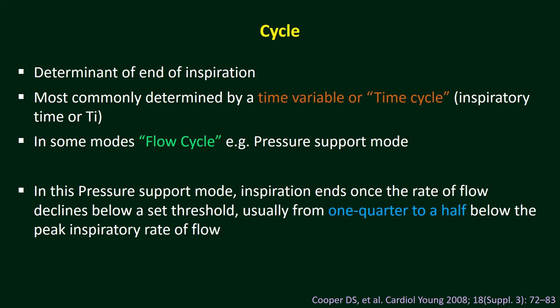But in some modalities there is flow cycle. Flow cycle is available in pressure support ventilation, or the pressure support mode of ventilation. In flow cycle, inspiration will end after delivering a percentage of flow. So, in pressure support mode, inspiration ends once the rate of flow declines below a set threshold, usually from 1/4 to 1/2 of the peak inspiratory rate of flow. Usually in the ventilator you may not need to set this because the ventilator by default sets 25 or 30%, and you may accept that, and you may not need to worry about it. So this is pressure support ventilation, which is actually patient trigger and flow cycle.